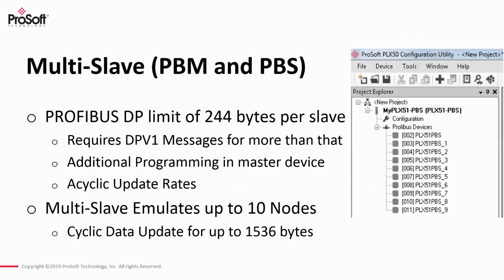So when we talk about Profibus multi-slave, again, like I mentioned, the limit of any Profibus DP slave device is 244 bytes of input data and 244 bytes of output data. For applications that require anything more than that, you typically had to take advantage of DPV1 messages, assuming that the slave device actually was a DPV1 device. And so that would allow you to do data table reads and data table writes that could be updated acyclically to the scheduled or the cyclic I/O data that was being transferred as part of that 244 bytes.